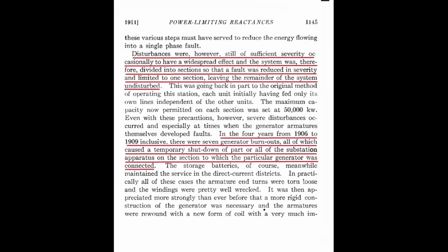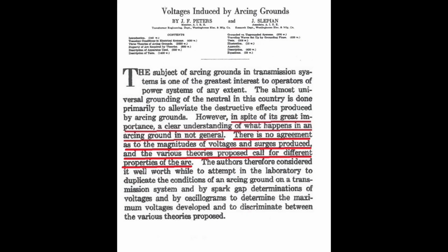shutdown of part or all of the substation apparatus on the section to which the particular generator was connected. In practically all of these cases, the armature end turns were torn loose and the windings were pretty well wrecked. The loss in revenue was immense. There were several similar but less catastrophic cases of outages at other generating stations where there was no obvious reason for the shutdowns. 11 years later, in 1923, the short circuit problem was still a great mystery.